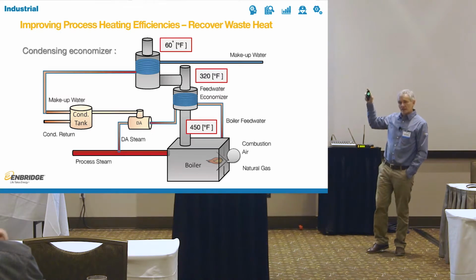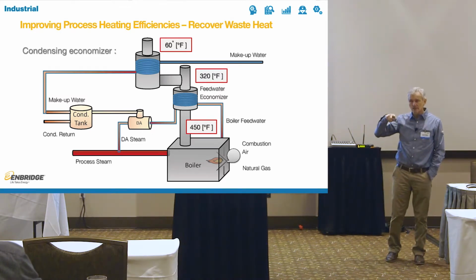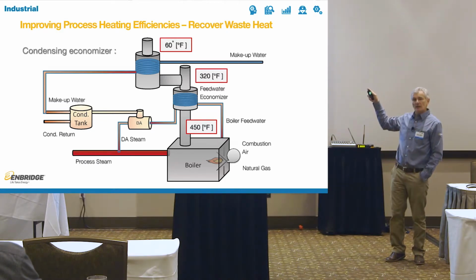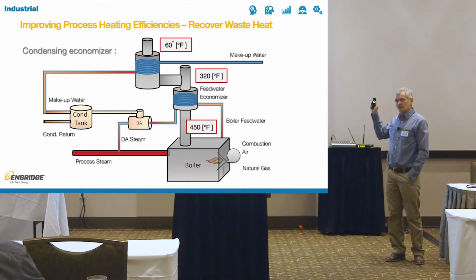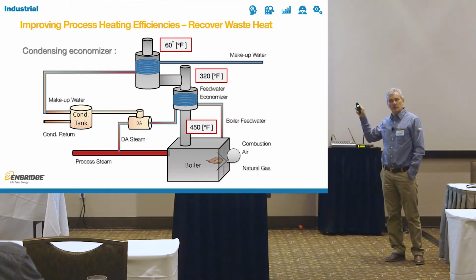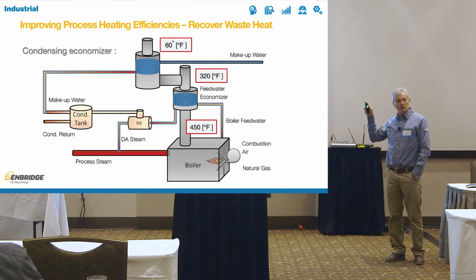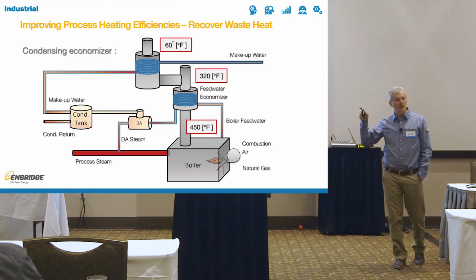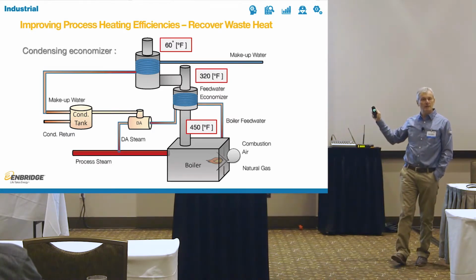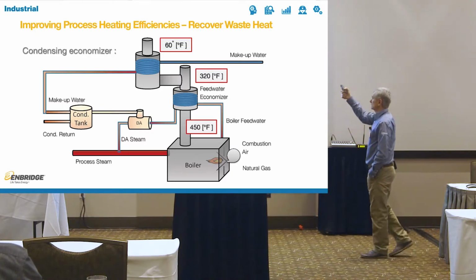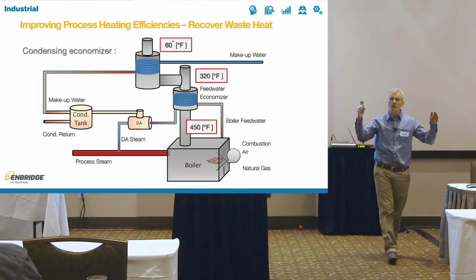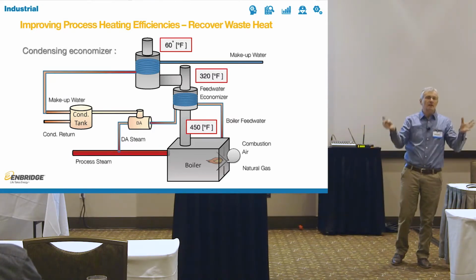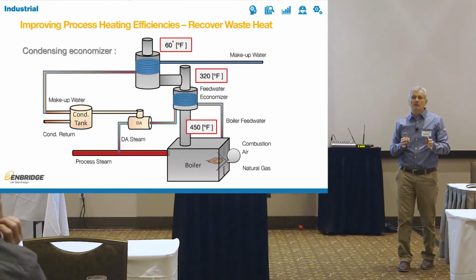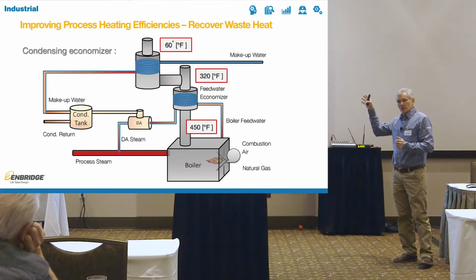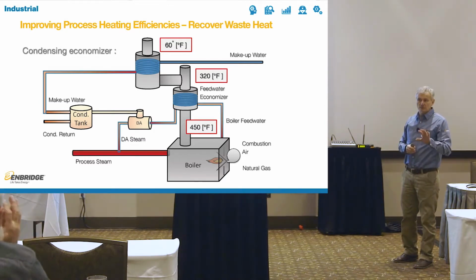The benefit of a condensing economizer, as we said, is that it can recover latent heat, which means it can condense, which means you can put cold water in it, and you'll get the flue gas temperature leaving down to as low as 60 degrees F. Now, if somebody is selling you a condensing economizer and tells you that they're going to get 60 degrees F flue gas out, I would not want to do that. I would want to keep it at about 90 to 100 degrees F, even if I leave some energy wasted. That's because I've seen installations where you go down to 60, 70 degrees F and you generate your own weather system on top of your building. When it comes out that cold, it immediately condenses and creates a little puddle around your stack. So I put 60 degrees F because it is technically possible, but I would leave it at 90 to 100 degrees F, and you're good to go there.